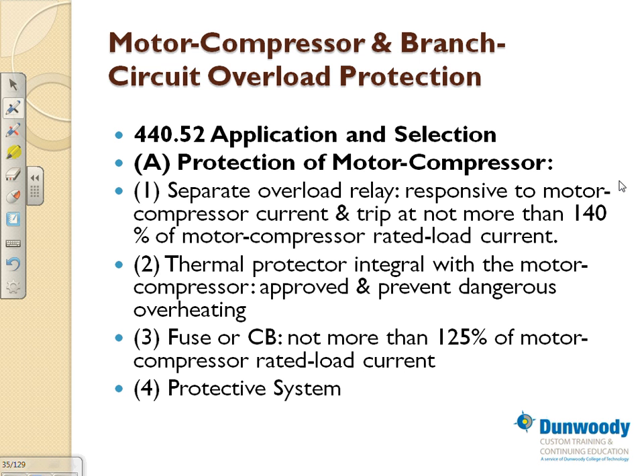Most of the time. If we are to get involved in sizing the overload, here's an example: 140% of the rated load amps. They allow you to go to 140% on a relay overload. You can also have a thermal protector integral with the motor, approved to prevent dangerous overheating, to protect it a second way. A third way is a fuse or circuit breaker, but don't go higher than 125%, or some type of protective system with the equipment. So there are different ways of protecting them. Most of the time, they have their own protection, so you don't have to mess around with it. It comes as a package, especially with chillers and compressors and so forth.